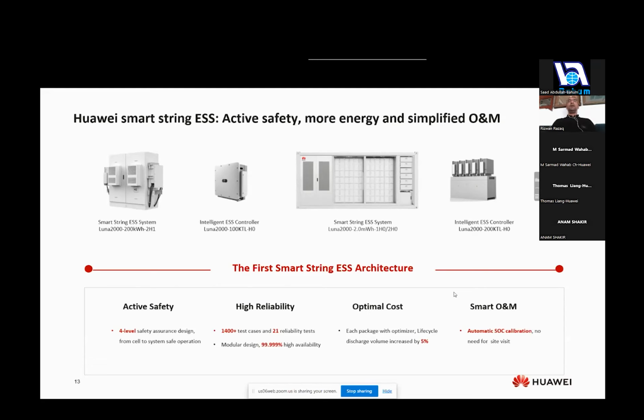Overall, our key value is active safety, with 4 levels of safety assurance in the design from cell level to system level. The second factor is high reliability. We have over 1,400 test cases and over 21 reliability tests carried out, providing our customers with a higher availability of 99.9%. The third factor is optimum cost. With each package with the optimizer, the life cycle discharge volume increases by around 5%. And the last factor is smart O&M, automatic state of charge calibration, and no need for site visits on a monthly or quarterly basis for the system to operate efficiently.